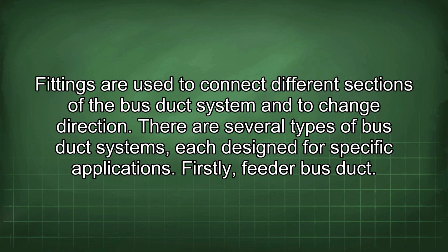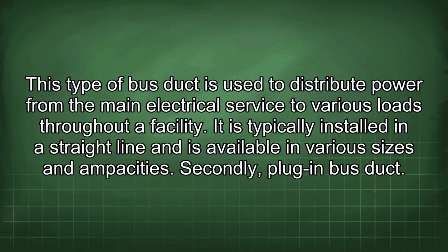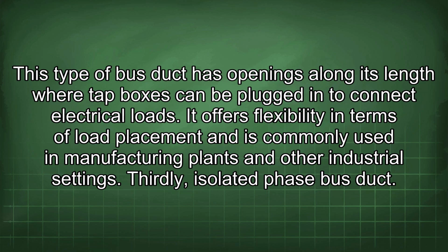There are several types of bus duct systems, each designed for specific applications. Firstly, feeder bus duct. This type of bus duct is used to distribute power from the main electrical service to various loads throughout a facility. It is typically installed in a straight line and is available in various sizes and ampacities. Secondly, plug-in bus duct. This type of bus duct has openings along its length where tap boxes can be plugged in to connect electrical loads. It offers flexibility in terms of load placement and is commonly used in manufacturing plants and other industrial settings.